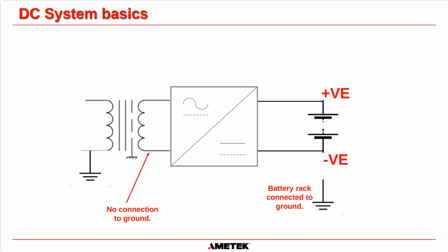It will usually be covered with some form of plastic coating, but it is metallic, so that battery rack has to be grounded. The battery rack will be connected to ground, and that usually will be the same ground in the plant that the primary of the transformer is connected to. But still, what I'm trying to say here is we still have absolutely no reference to ground on the output here whatsoever at this time.